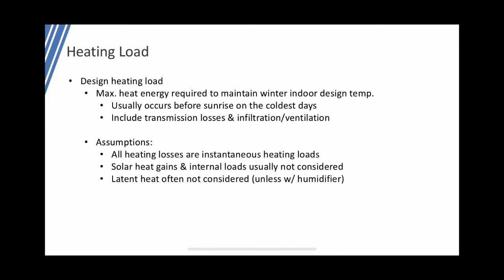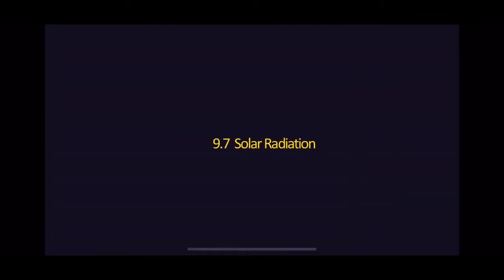Solar heat gains and internal loads are usually not considered in heating load calculations — we don't account for sunlight entering the space or internal loads such as occupants, servers, or computer workstations that emit significant radiation. Latent heat is also often not considered unless a humidifier is present. That concludes the heating load section; now we move to solar radiation.